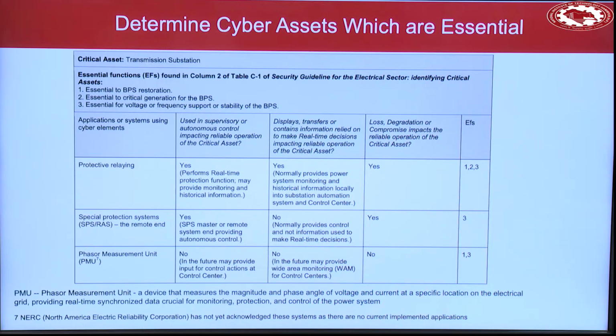So we do use relays in power systems to help control the system. When there's an overload on a line, we want to trip it down - if you don't, it will destroy your component. At the time of supervisory control, when feeding data, you also need to know which lines are open and which are closed. Does it help in making real-time decisions? Yes - that's how you know if there's demand in a certain region, and if a line is open, you want to close it, making the circuit so supply can be provided in that region.